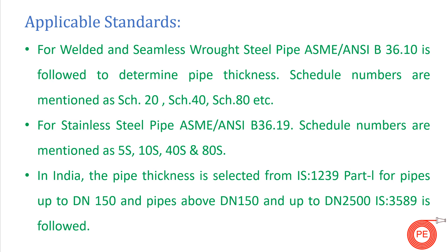What are the applicable standards? For welded and seamless wrought steel pipe, ASME B36.10 is followed to determine the pipe schedule number. For stainless steel pipe, ASME B36.19 is used. The difference is that schedule numbers for stainless steel pipes are followed by the letter 'S'. So if you see a schedule number with an 'S' suffix, it refers to stainless steel pipe referenced from ASME B36.19.